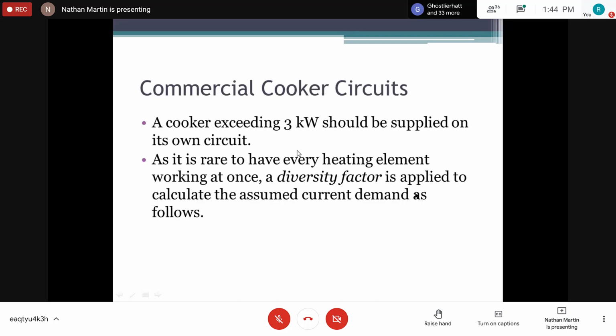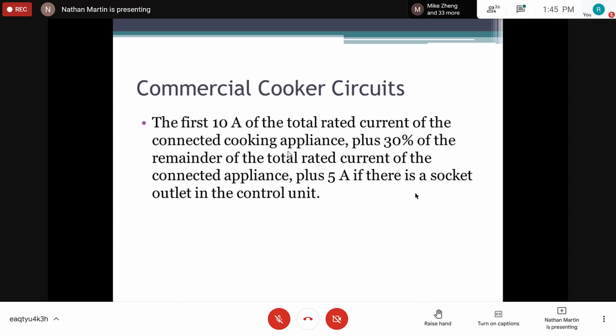Commercial cookers, right? A cooker exceeding 3 kilowatts should be supplied on its own circuit, right? So we're not talking about your stove at home, but a commercial cooker that is above 3 kilowatts. As it is rare to have every heating element working at once, a diversity factor is applied to calculate the assumed current demand as follows, right? The first 10 amps of the total rated current of the connected cooking appliance, plus 30% of the remainder of the total rated current of the connected appliance, plus 5 amps if there is a socket outlet in the control.